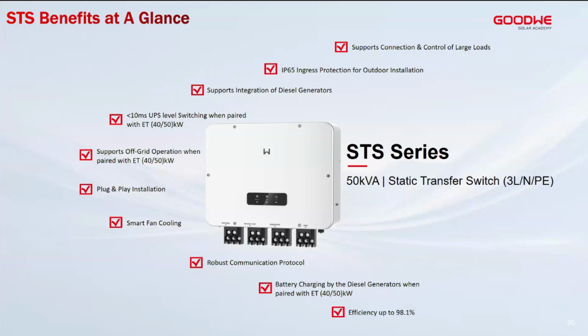It supports diesel generator connections, as I mentioned before. So basically, it integrates the power from the inverter, connects to the critical loads, connects to the diesel generator, and also connects to the grid incoming lines. So it can support both critical and non-critical loads through the STS. The level of switching is under 10 milliseconds for a single inverter. We keep it under 10 milliseconds. So in case the grid fails, the transition time is very seamless.